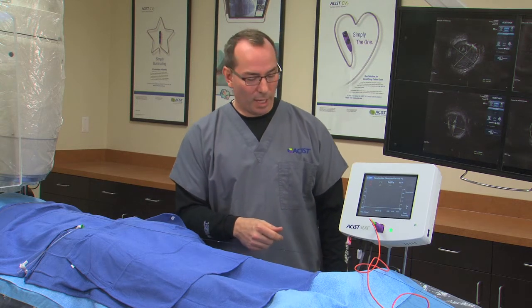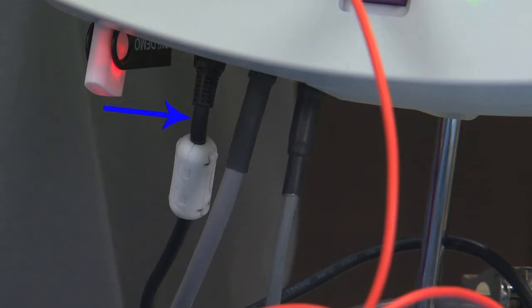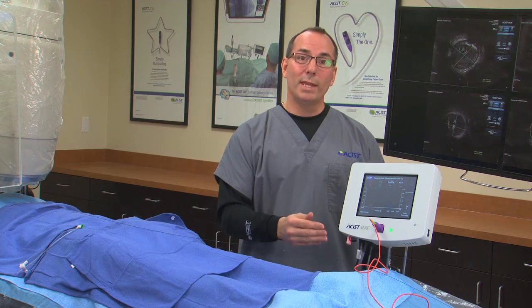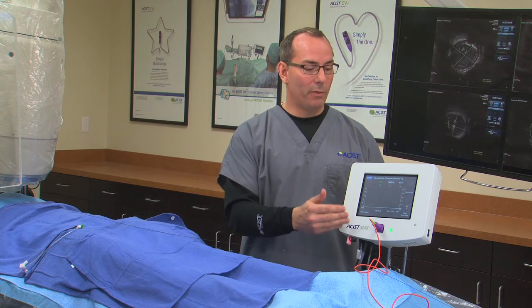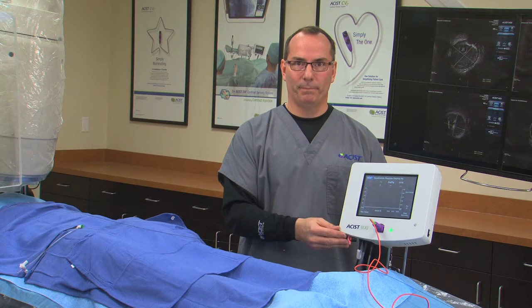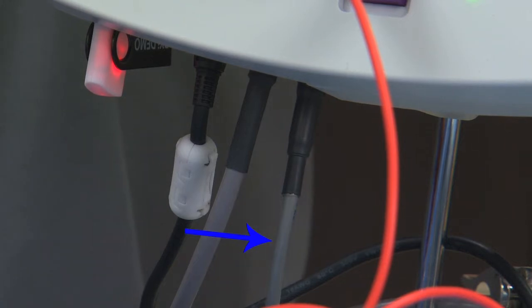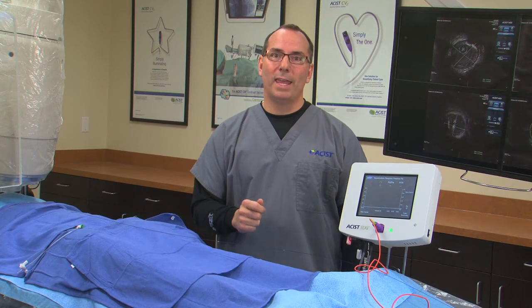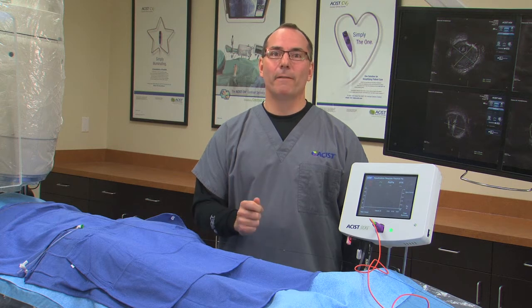The RXi Console has three cables on it. The power cable, which supplies the unit with power. The second cable brings the patient's aortic pressure into the console for FFR calculation, so then we can see the pressure waveforms of the patient on the system. The third cable is actually for exporting the Navvus catheter pressure into the cath lab hemodynamic system. This becomes important when the cath lab hemo system has the FFR software.